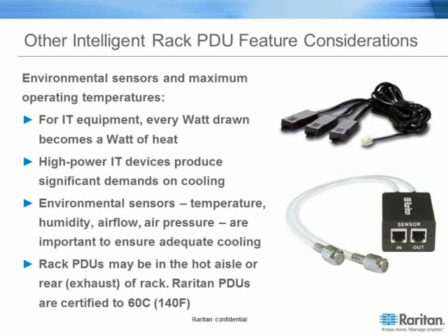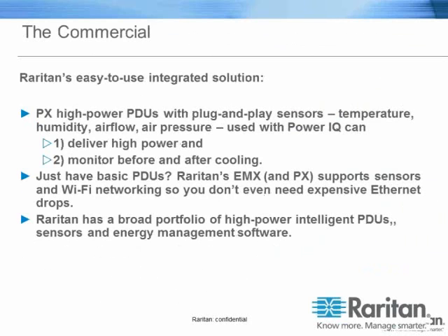So it's important to have environmentals in your data center. On Raritan PDUs, we can deploy up to 8 temperature and 8 humidity probes, as well as airflow and air pressure sensors. It's important to know you're getting airflow to the right spot, and in a chimney system with outside air economization, what your air pressure is. We have that ability off the front of our PDUs to manage, report on, and set thresholds for environmentals, keeping you in the know in the data center.